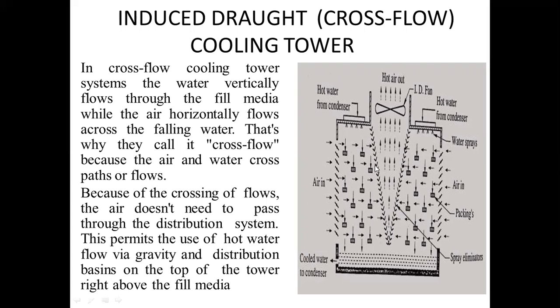There are baffles in the V shape which eliminate the water. Right, water is sprayed here, air is moving in this direction. In the cross flow cooling tower system, the water vertically flows through the fill media while air horizontally flows across the falling water. That's why they call it cross flow, because the air and water cross paths or flows.